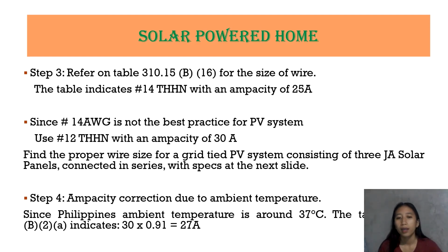Okay, so ang sabi natin, di ba, is find the proper wire size for a grid-tied PV system consisting of 3 JA solar panels connected in series with specs at the next slide natin. Okay, so step 4 is ampacity correction due to ambient temperature. Dito sa Pilipinas, since Philippines ambient temperature is around 37 degrees Celsius, pupunta tayo sa table. Sa table, sinasabi doon na 30 times 0.91 is equal to 27 amperes.